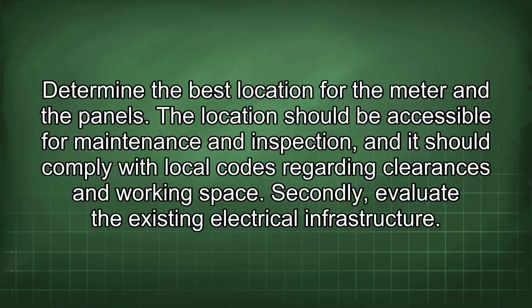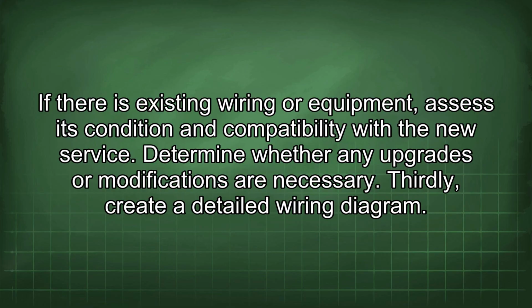The location should be accessible for maintenance and inspection, and it should comply with local codes regarding clearances and working space. Secondly, evaluate the existing electrical infrastructure. If there's existing wiring or equipment, assess its condition and compatibility with the new service. Determine whether any upgrades or modifications are necessary.